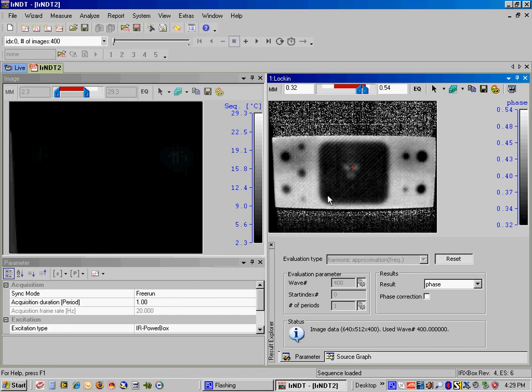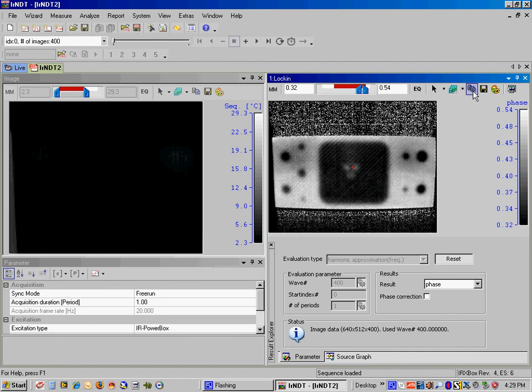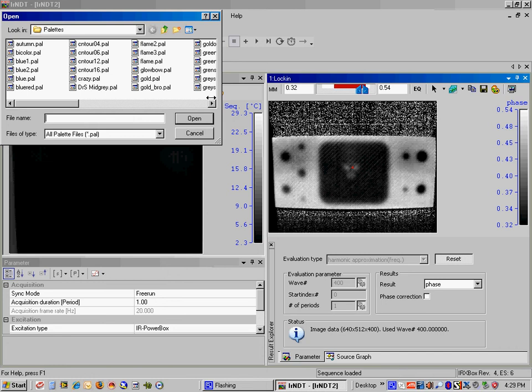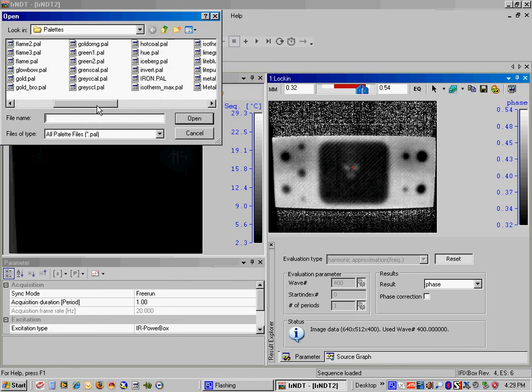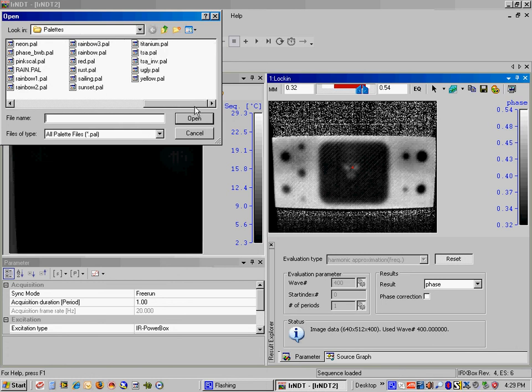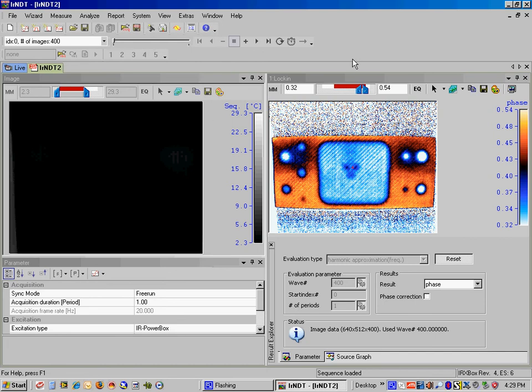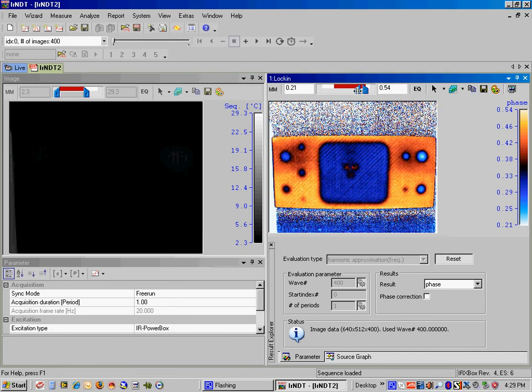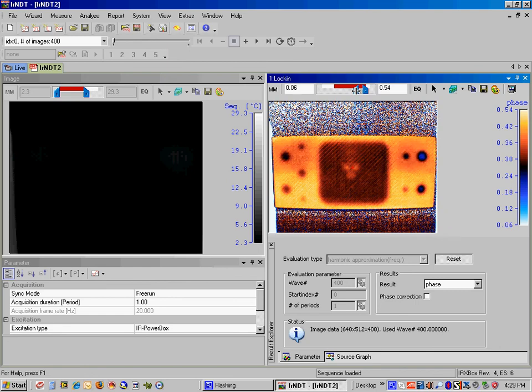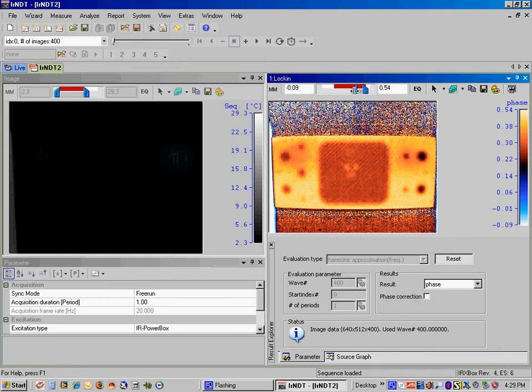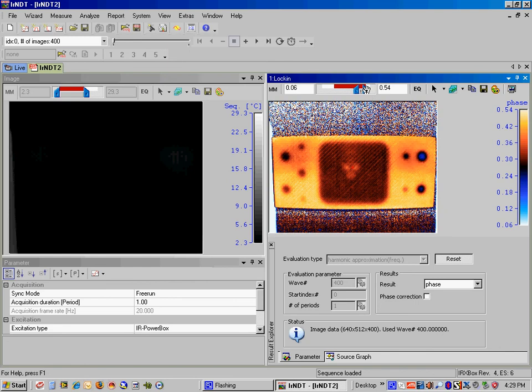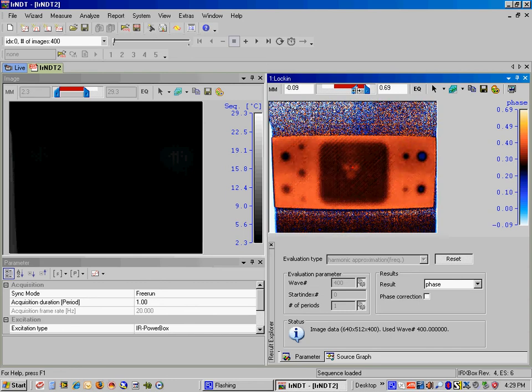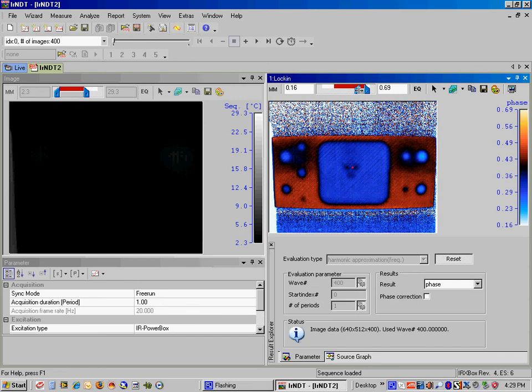We've also got some other options for viewing this image. You can select a different palette to give us a little bit different color scheme. I'm going to select TSA, which gives us a full range from blue to yellow. Different intensities. Different ones give different effects. So you can more clearly see the flaws here. All right, so that's using the lock-in thermography wizard.